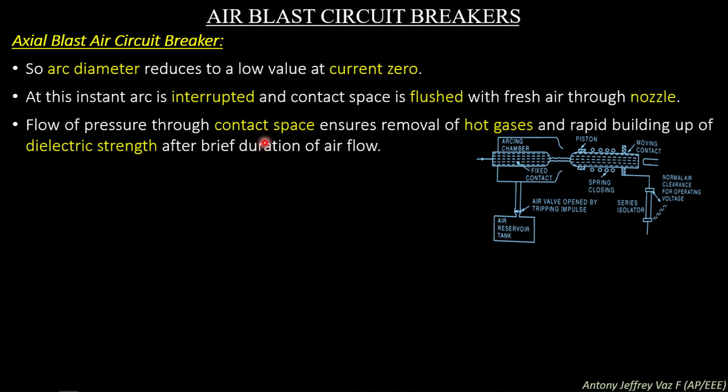The flow of pressurized air through the contact space ensures removal of hot gases and rapid building up of dielectric strength after a brief duration of airflow. Since the fresh air compressed in the air reservoir tank is fed into the arcing chamber after the arc has struck, this fresh air has a much better dielectric strength than the arc air.